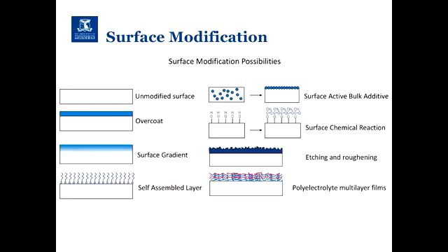If you have your unmodified surface, you can put a surface coating on top of it. Something like that is dip coating. Have you ever had a piece of metal with a polymer, plastic around it? That's dip coating. You put your device in a liquid, could be a polymer, you dip it in, you dip it out, and it's a coated surface. A very easy way to change the properties of what our body sees of that material.